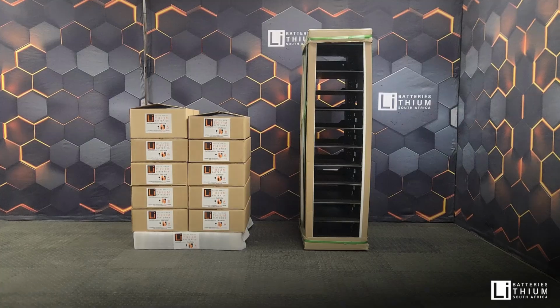So our battery ranges from 23 to 88 kilowatt hours per rack, and you can parallel up to 60, which gives you 5.2 megawatts. When you're connecting high voltage, the modules are connected in series instead of parallel. So all this means is your voltage goes up and your amps remain the same, whereas on low voltage, your voltage remains the same and your amps go up. So without further ado, let's start the unboxing.